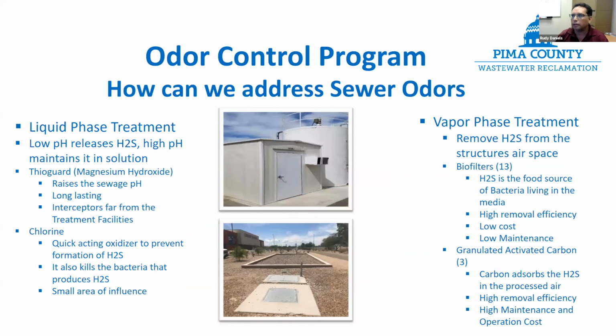And so how do we address sewer odors? Well, within our department, we have a liquid phase and a vapor phase. Within the liquid phase, we are using magnesium hydroxide, also known as Thioguard, that is very long lasting. It's very potent in reducing H2S levels within our large line interceptors very far from our treatment facilities.